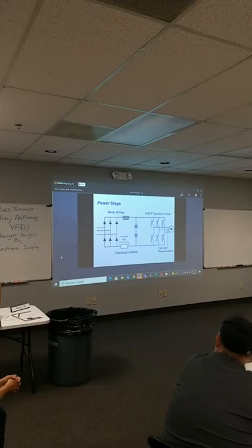If you remember, he showed that big formula for what your DC bus is supposed to be. There's really just a simple rule of thumb: your DC bus voltage will be about 1.44 times your incoming voltage. So if you've got 240 coming in, I'm gonna pull out my handy dandy calculator here, 240 times 1.44, your bus voltage should be around 345, 350, somewhere in that range. So that's a rule of thumb to remember: your incoming voltage times 1.44 is what you should see on your DC bus.